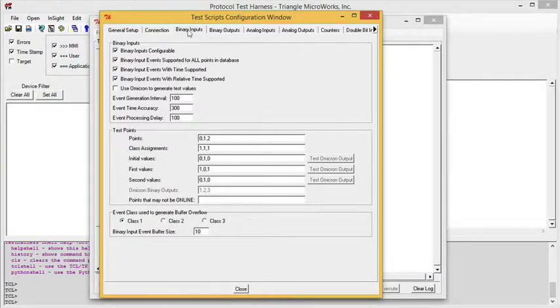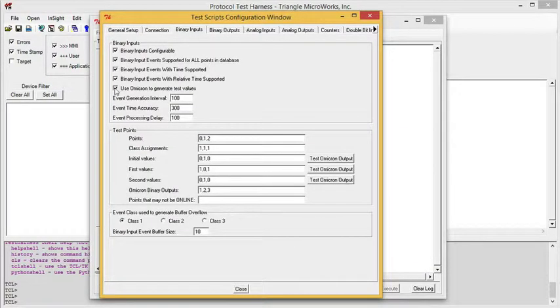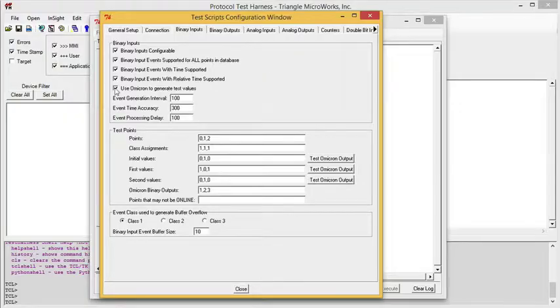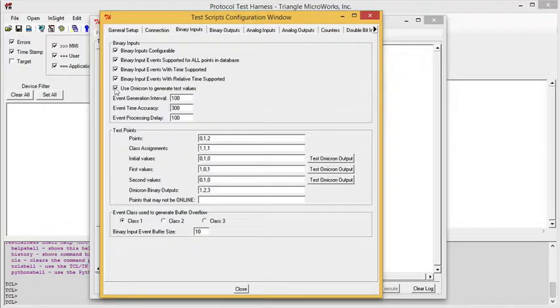If we look on the input tabs, there's an option to use an Omicron CMC 156, 256, or 356 to generate the test values. This option can really aid with automated testing, as the test harness will send commands to the Omicron to set up test conditions, and then read the values and see if it got the expected results.